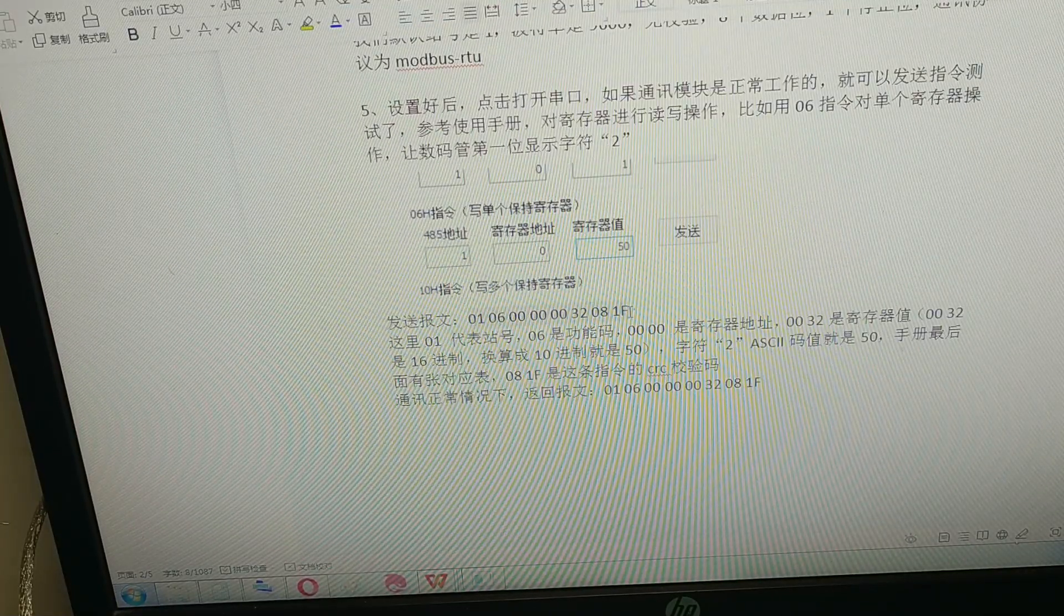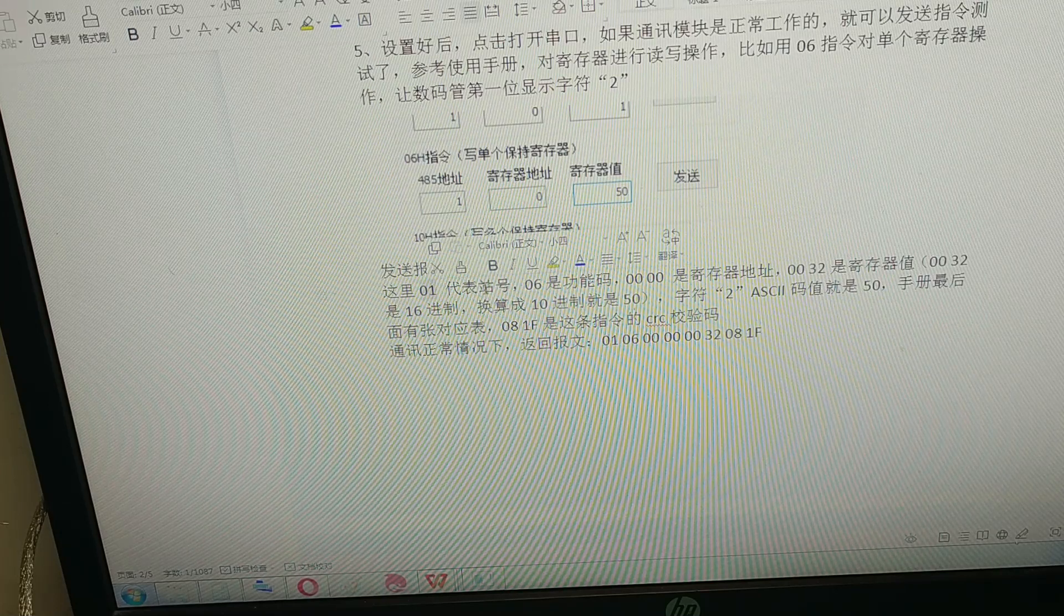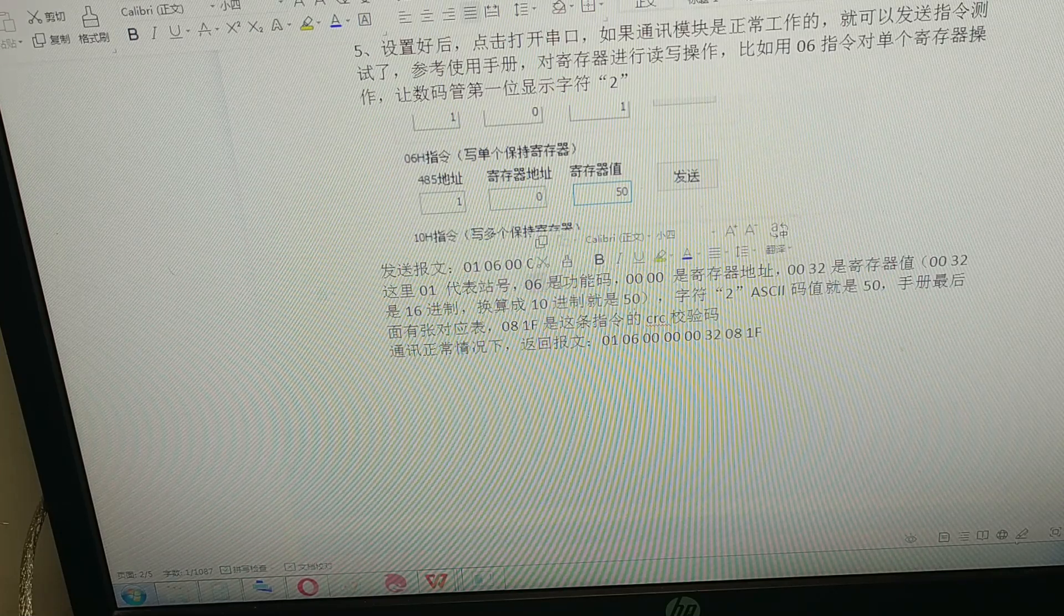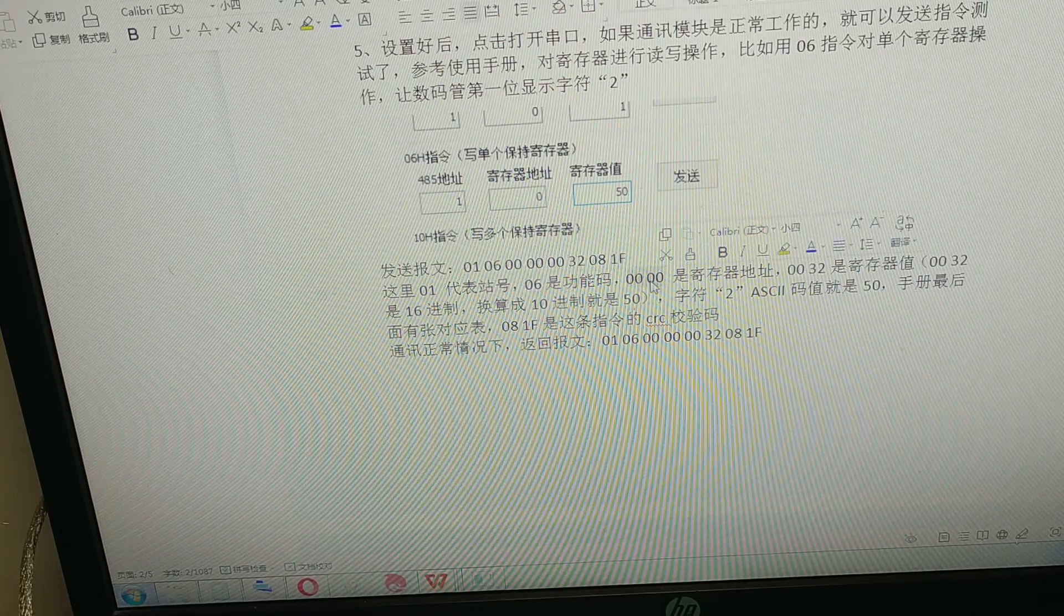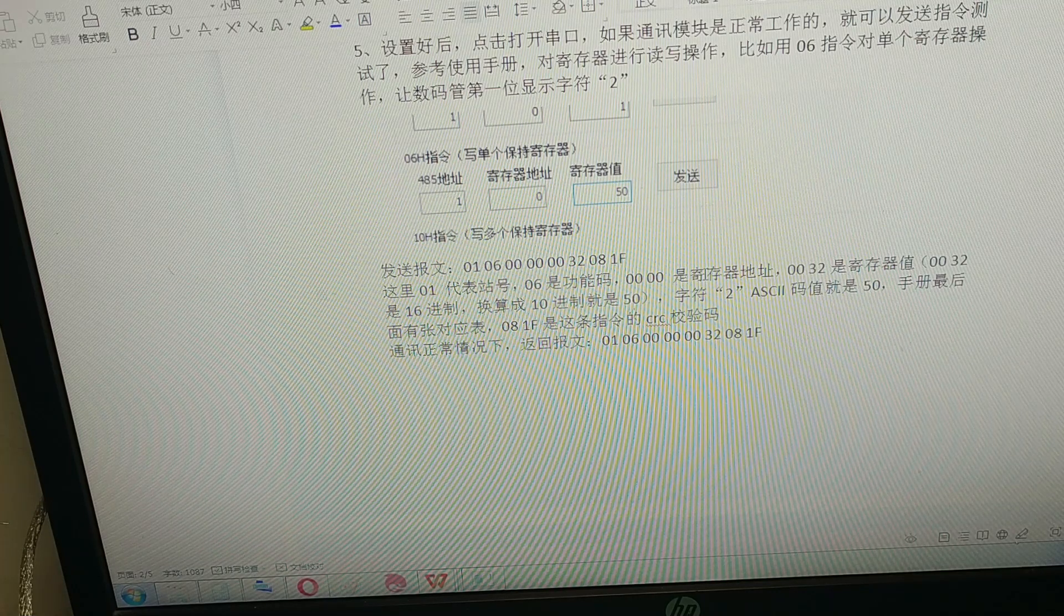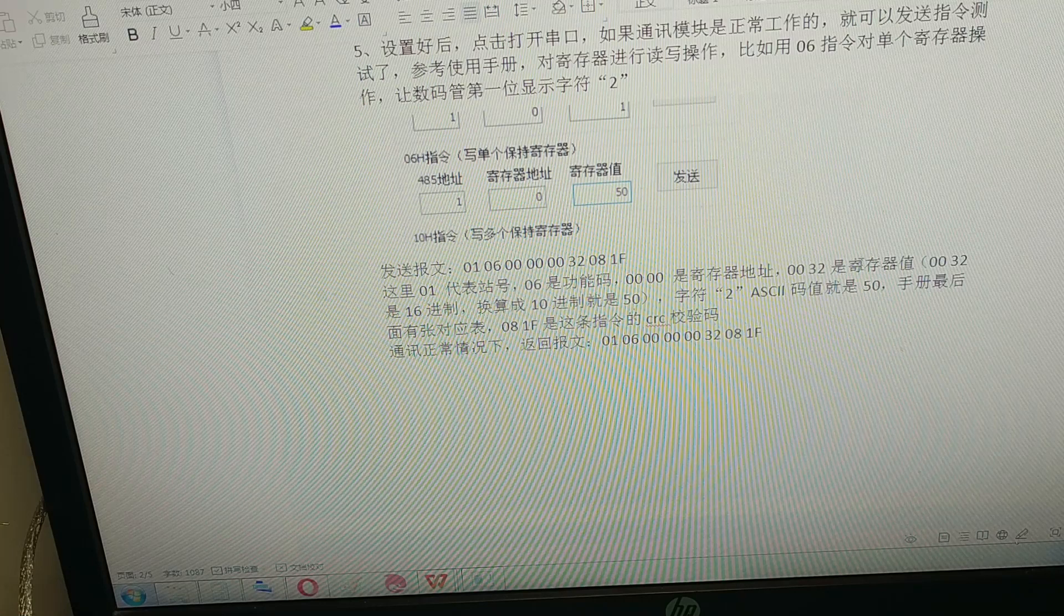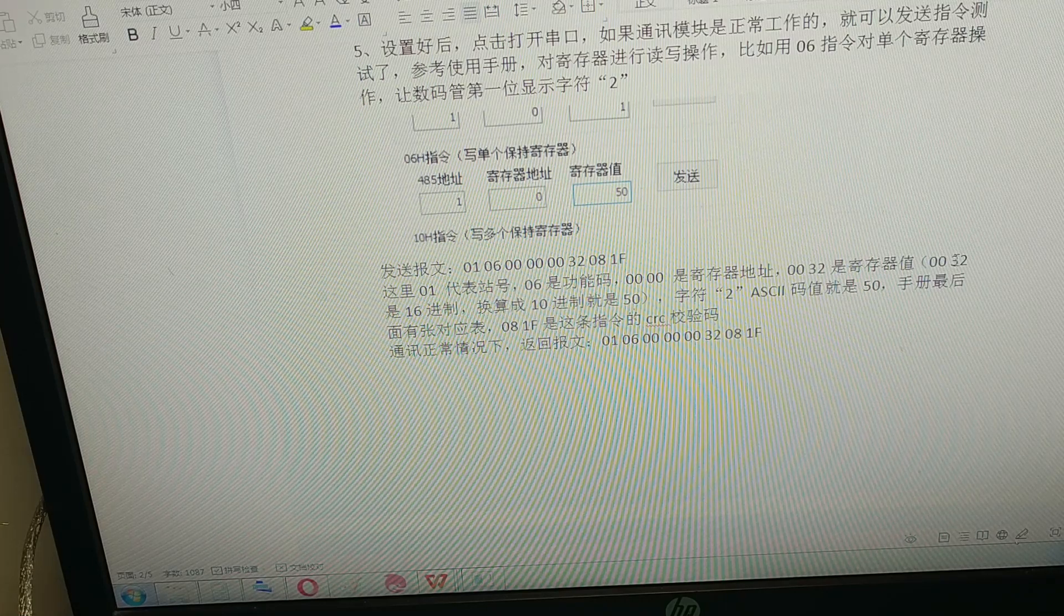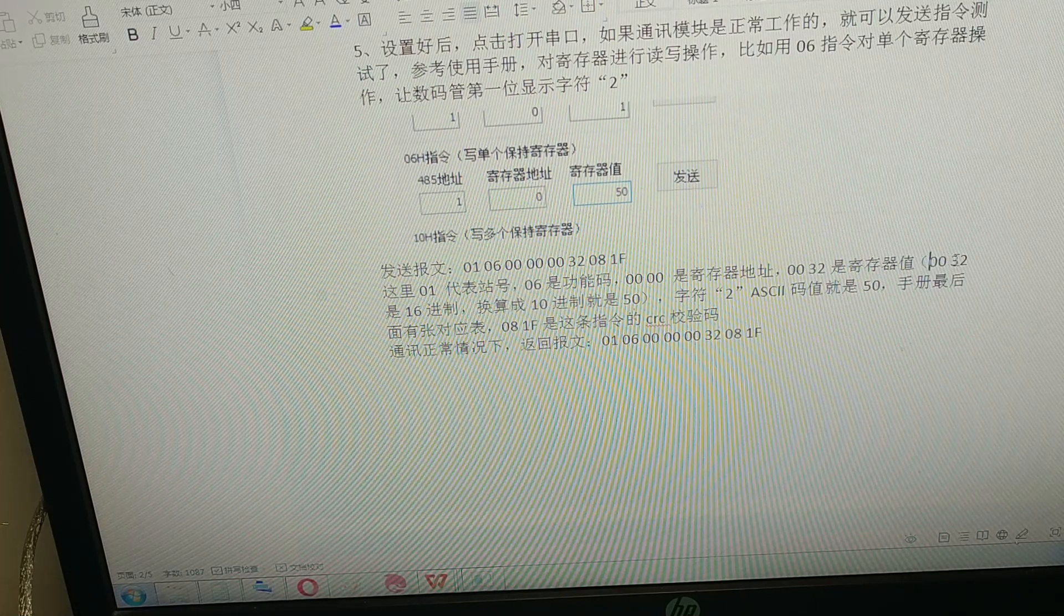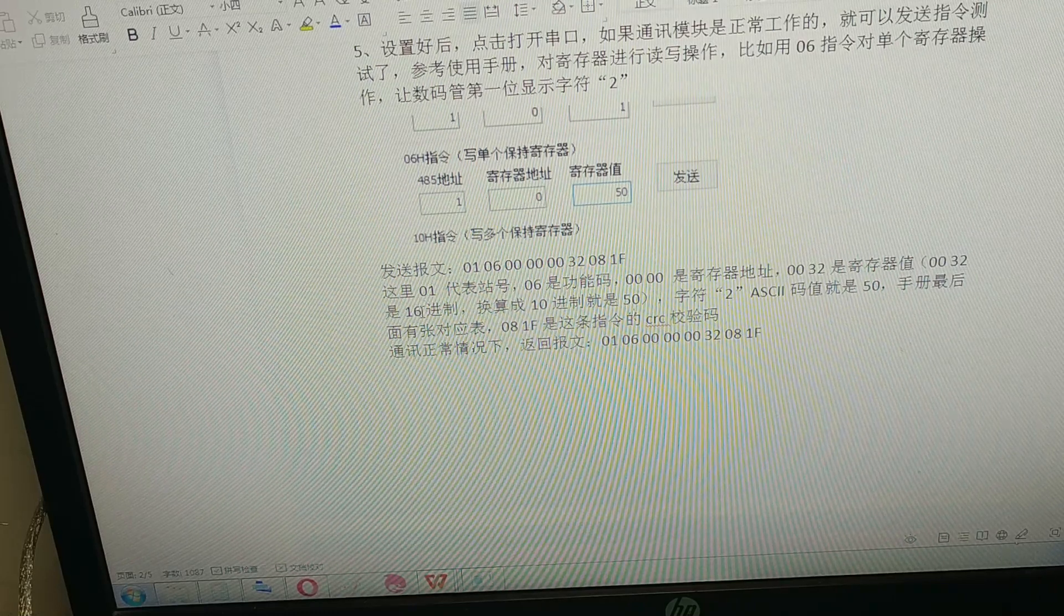The screen 01 presents station number and 06 presents the function number. Four zeros is the address of the register and 0032 is the value of the register. It also says the 32 is a hex format.